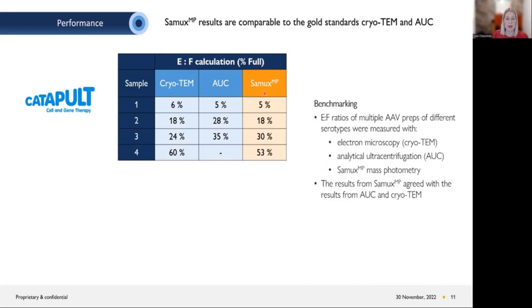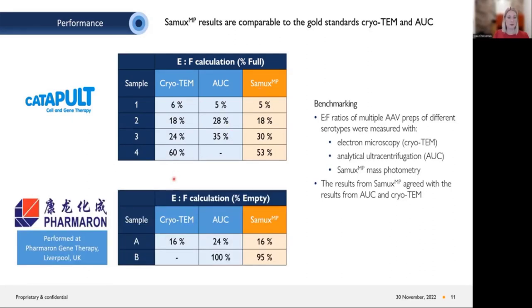We benchmarked the empty/full ratio from the SamuxMP against the gold standards: cryo-TEM and AUC. This was done in collaboration with the Cell and Gene Therapy Catapult in London. Across different empty/full ratios from 6 to 60% full, we obtained very similar results to cryo-TEM and AUC, showing our measurement is accurate. We also did a similar study with Pharmaron, comparing two samples with SamuxMP against cryo-TEM and AUC, and at very high empty ratios, our results again compared nicely to the gold standards.